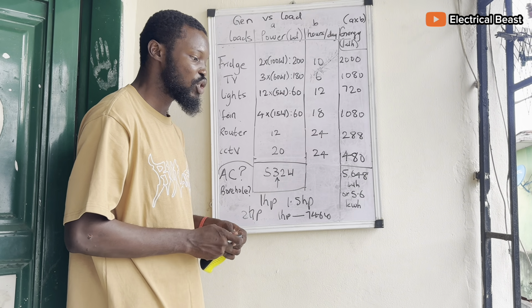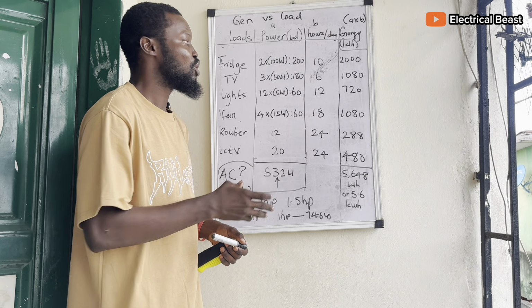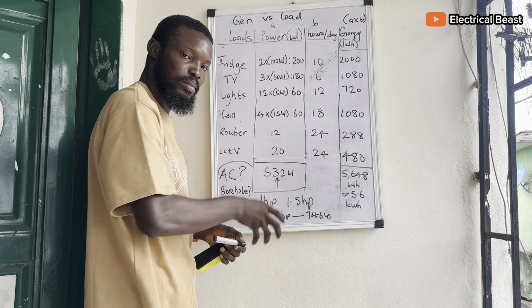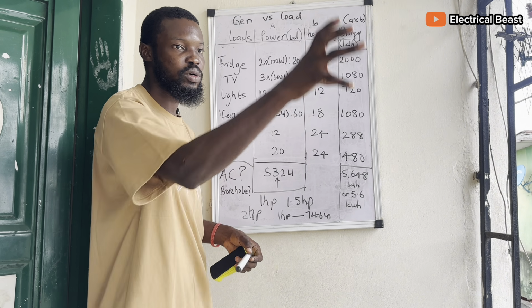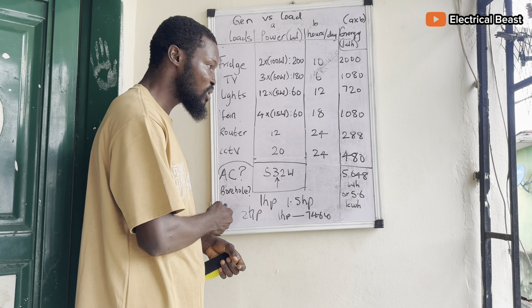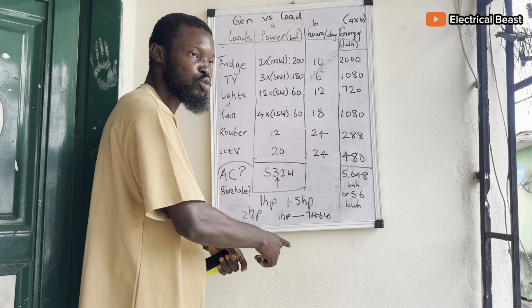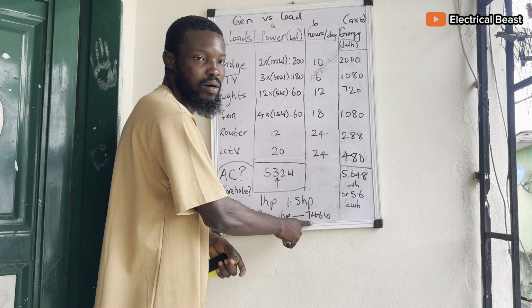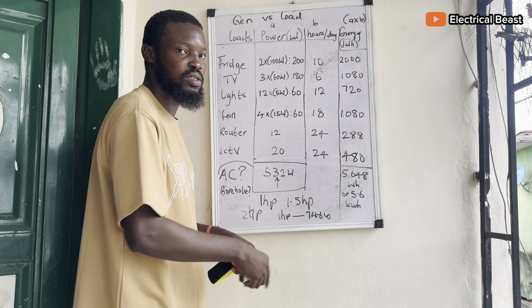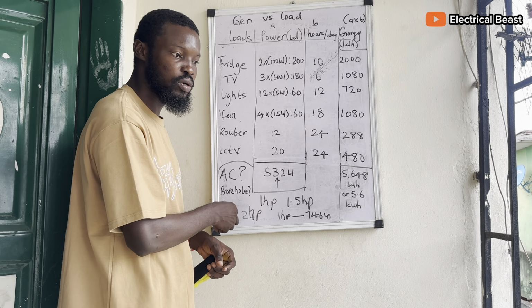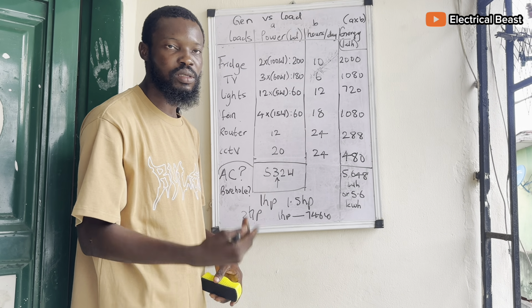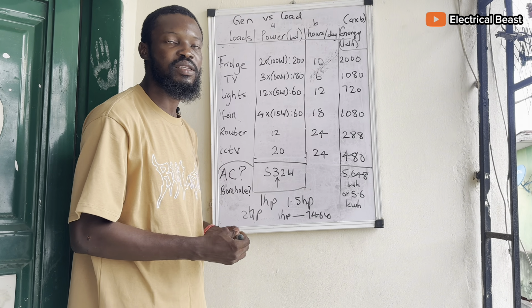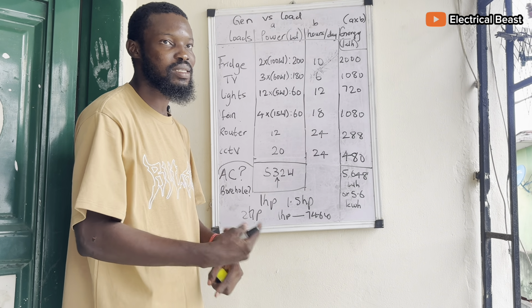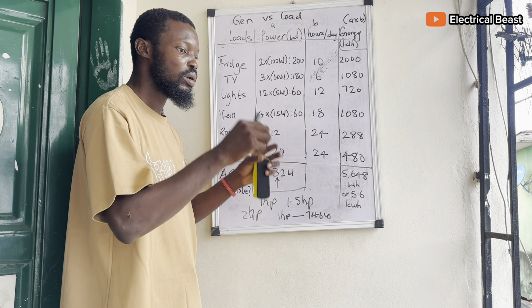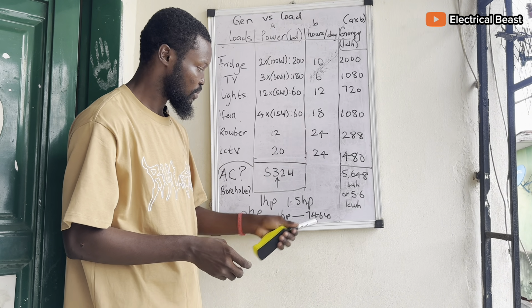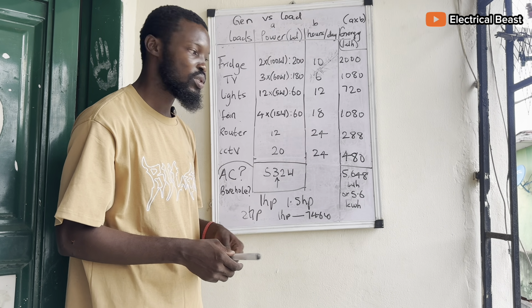Very, very important. Unless you have it in mind that you're not going to switch on all the loads at the same time. Maybe if you want to put on your AC, you can switch off other loads so that you have space for your AC to run up to 3 times its running power before it gets back to the 746 watts. The same applies to your borehole, because these are inductive loads. They have coils and all that, and they're very sensitive loads. They need 3 times the power to be able to start the motor, before it gets back to its normal power consumption.